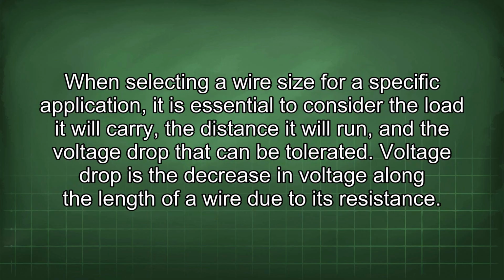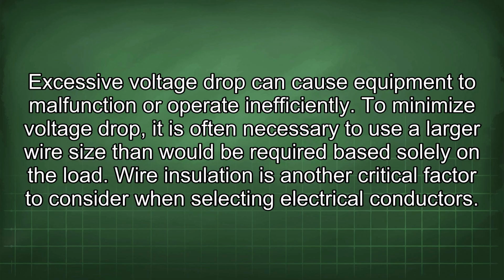When selecting a wire size for a specific application, it is essential to consider the load it will carry, the distance it will run, and the voltage drop that can be tolerated. Voltage drop is the decrease in voltage along the length of a wire due to its resistance. Excessive voltage drop can cause equipment to malfunction or operate inefficiently. To minimize voltage drop, it is often necessary to use a larger wire size than would be required based solely on the load. Wire insulation is another critical factor to consider when selecting electrical conductors.